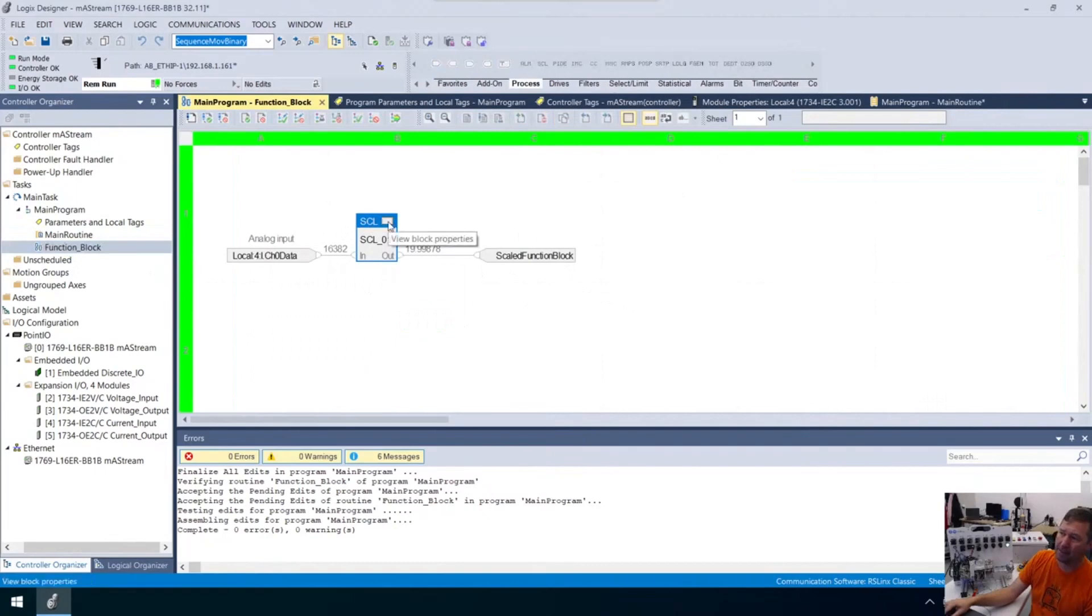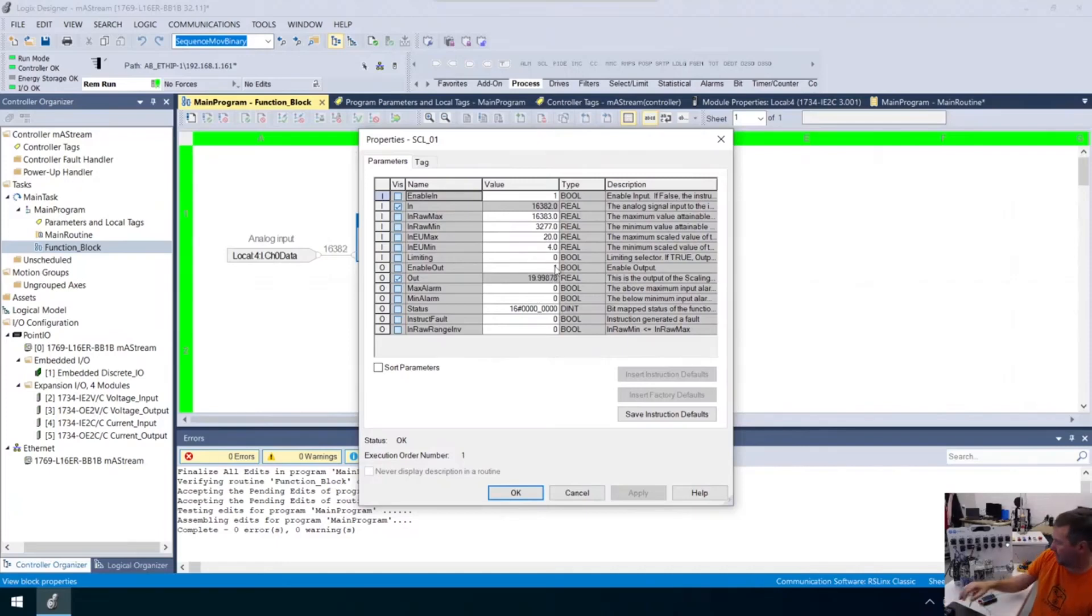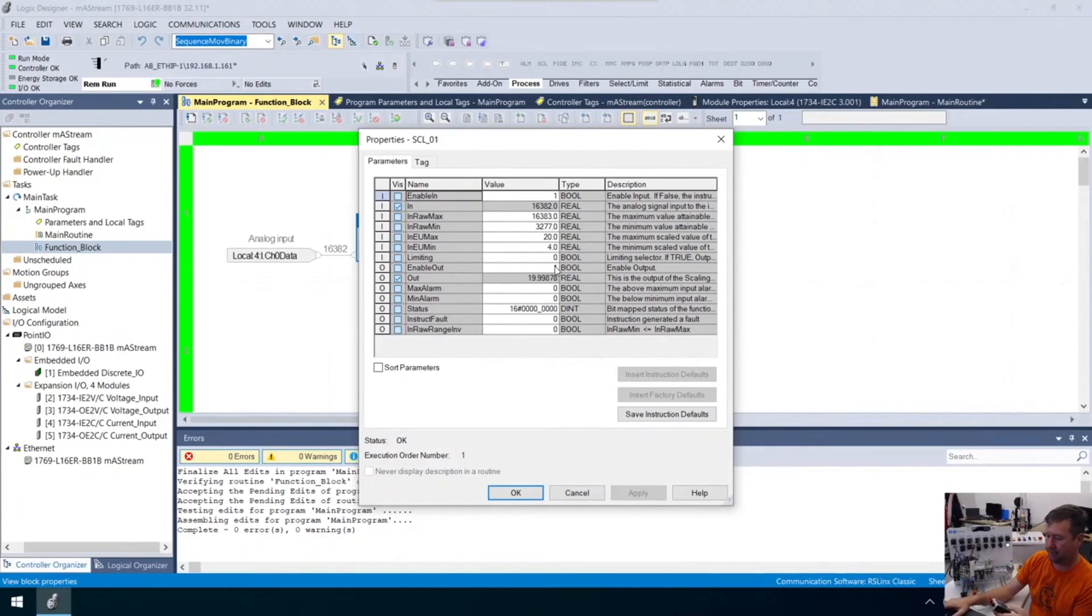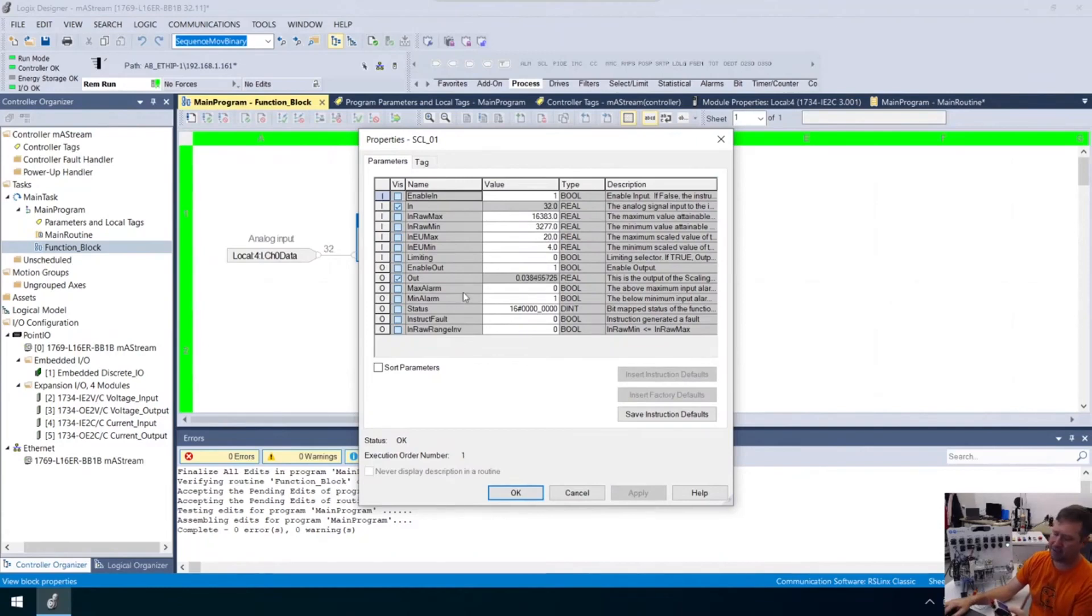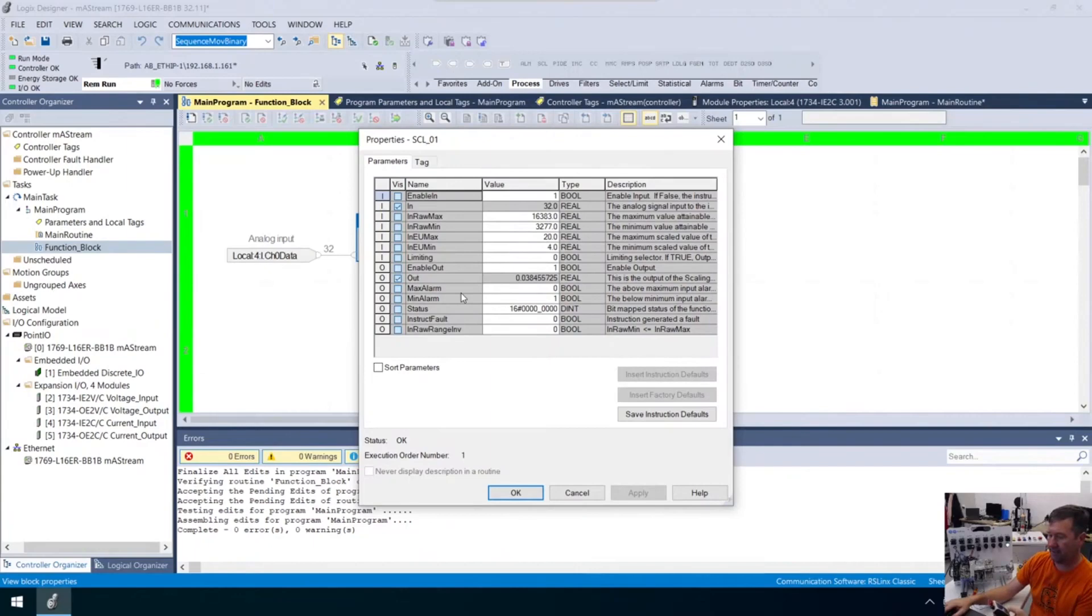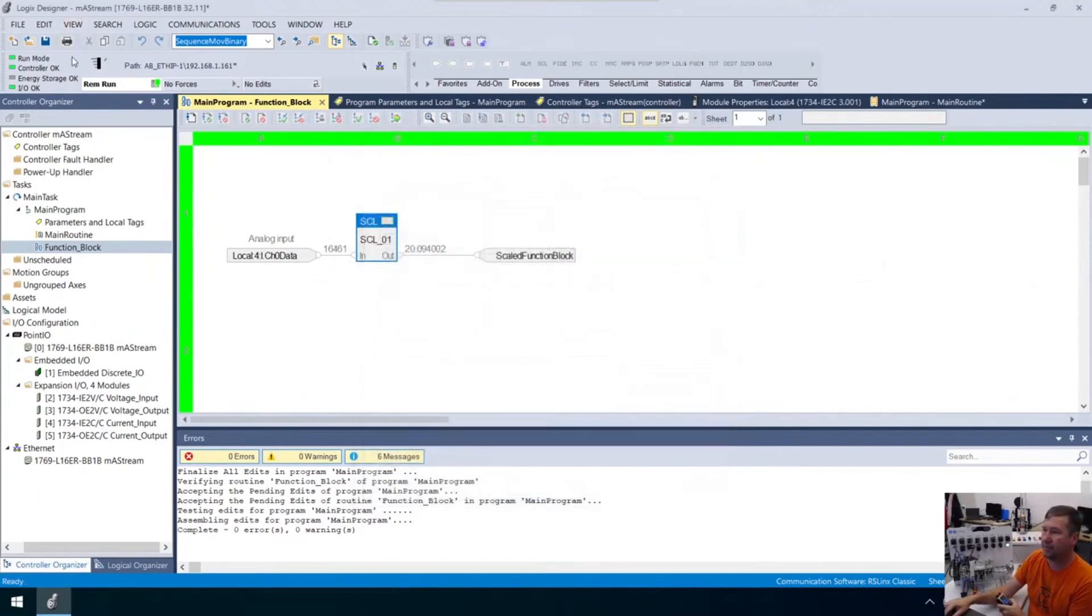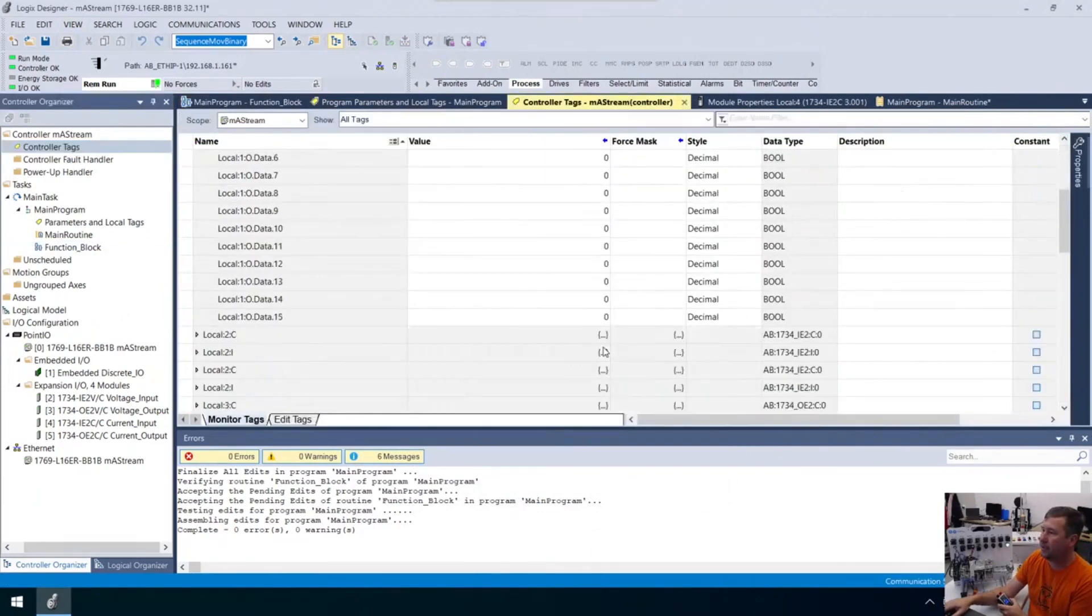While we're here, let's look at a couple other things. I'm going to take my range back to zero to 22 milliamps because the analog simulator by default is not going to let you go out of range. I just changed it back to zero to 22 milliamps. I'm going to go back in here. We're right at that 20 milliamp mark. I'm going to bump it up to 20.1.